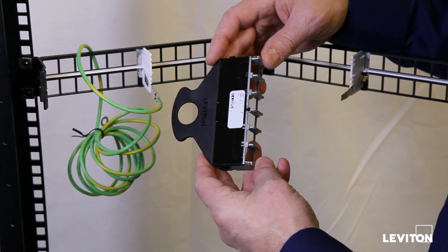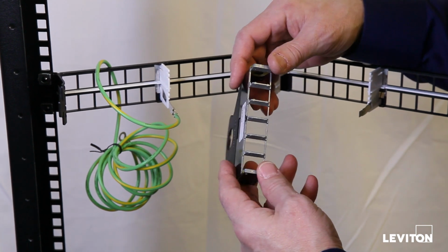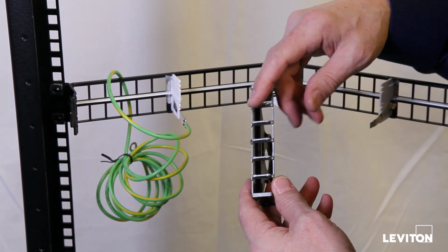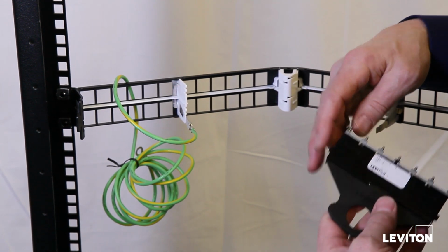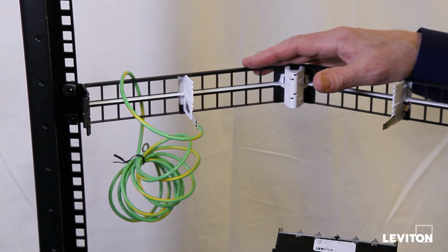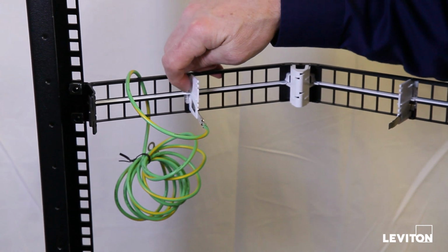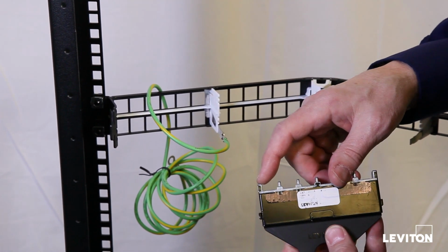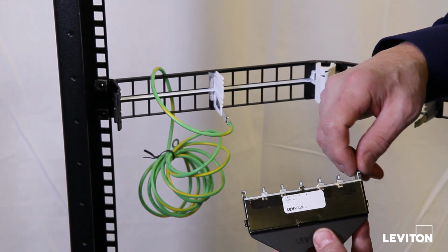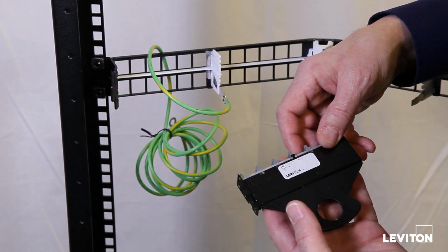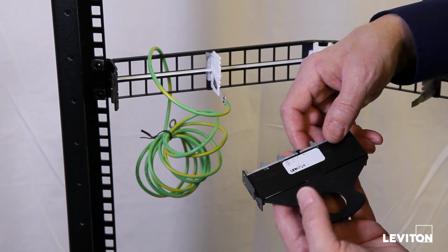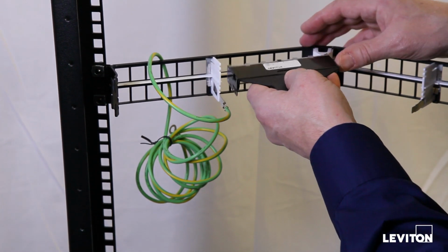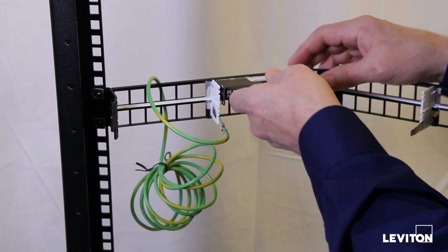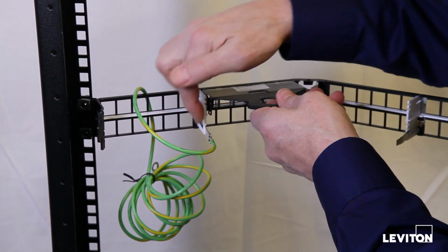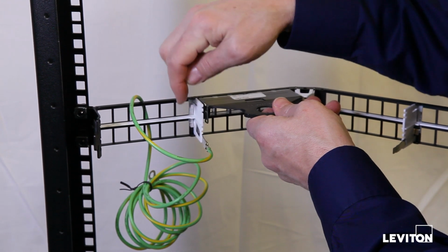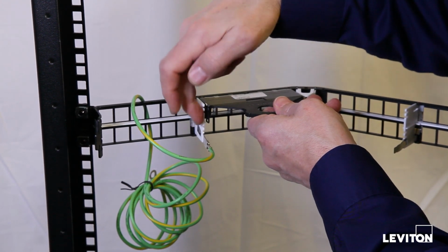E2XHD angled and flat panels can accept cassettes loaded with shielded twisted pair cables, unshielded twisted pair cables, or fiber optic modules. The cassettes plug directly into the 8 ports on the panel. When shielded jacks are installed into the cassette, a bond is created between the metal front of the cassette and the jack body. When the cassette is inserted into the panel, the metal front makes contact with the bonding spring and forms a bonding connection between the metal front of the cassette, the bonding spring, and the earthing tab. The earthing jumper is then attached to the rack bonding bus bar with the earthing tab completing the connection.